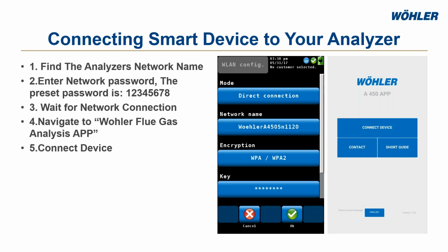And then at that point, you can navigate to the Wöhler Flue Gas Analysis app. You would hit Connect Device, and then it's going to come up and say flue gas analysis. At that point, you're going to start mirroring everything that the analyzer sees. You're connected to the app. You can start seeing readings. You can send reports to yourself, save readings, graph, whatever you want to do with the app.